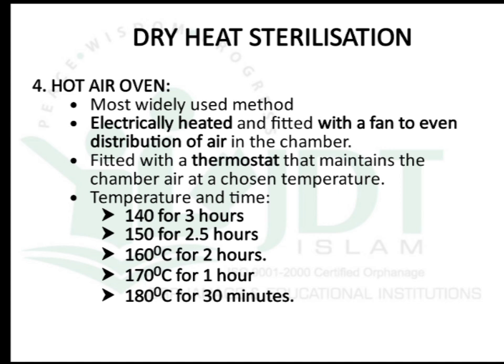The temperature and time conditions for a hot air oven are: 140°C for 3 hours, 150°C for 2.5 hours, 160°C for 2 hours, 170°C for 1 hour, and 180°C for 30 minutes. As temperature increases, the sterilization time can be reduced.